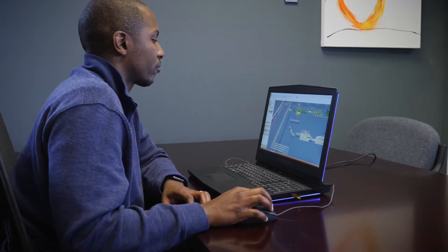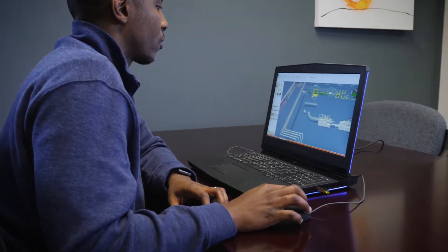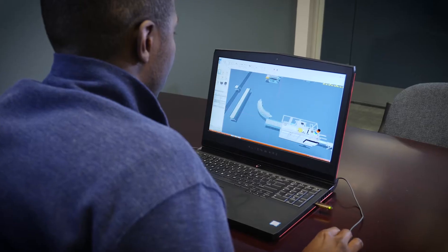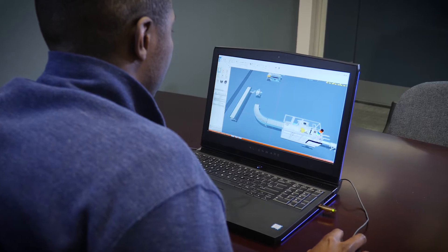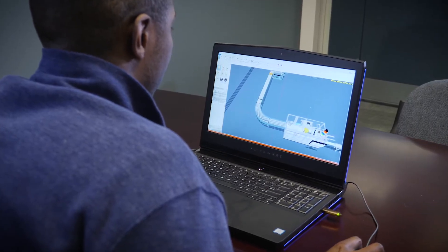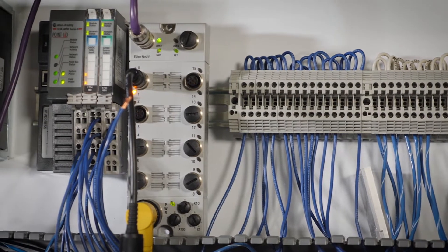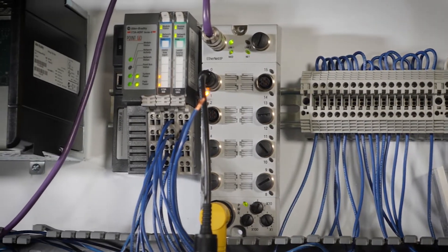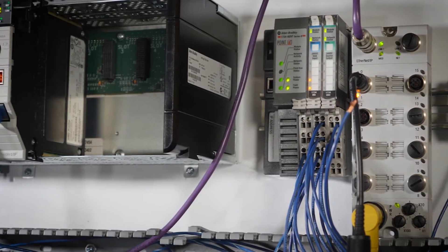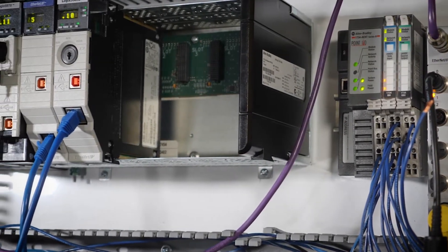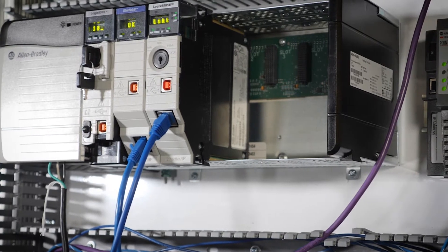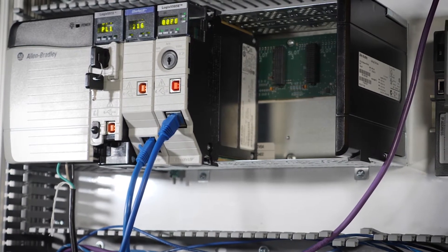The process of creating a digital twin begins with importing three-dimensional machine models into Emulate 3D and adding the mechanical functionality of the process and material handling systems. Next, we connect each of the equipment centers to the corresponding program tags inside the Logix PLC. Finally, we embed the machine HMIs in the model using a web browser that connects to the HMI server.